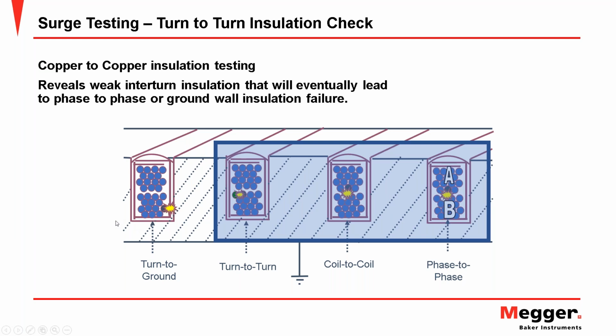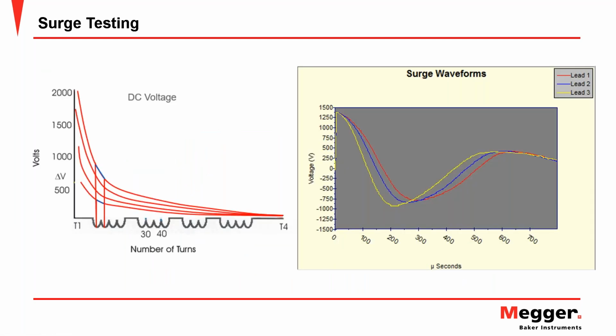And so when I do MEGGER testing, insulation resistance evaluation, whether it's low voltage or even high voltage with the step voltage test, I'm only evaluating this portion of the insulation, not the individual turns or the coil to coil or the phase to phase. So surge testing enables us to look at that insulation, which is also stressed again during those start and stop intervals, switching intervals.